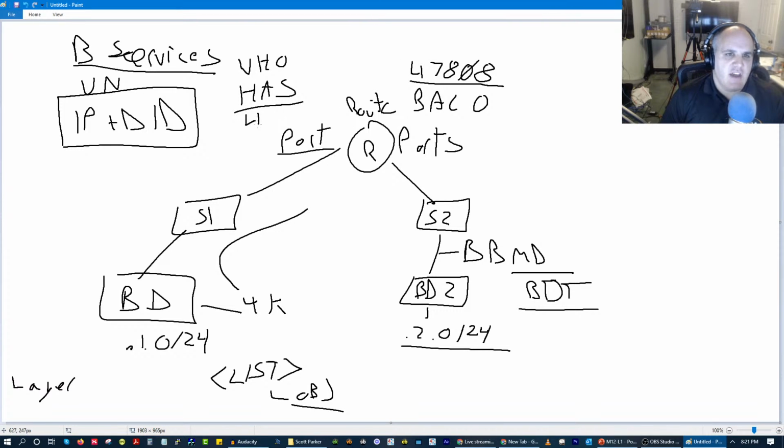47808 and another set up as like 47809. And this is where routing needs to take place. And in your routers, you will say, okay, we need to route to this port as well as this IP address. So it's a very simple fix, but if you're not cognizant of it and you go to troubleshoot and you're like, I'm pinging 47808, but I'm not getting any traffic, that would be why. And it's just a matter of realizing that you have routes and things like that.